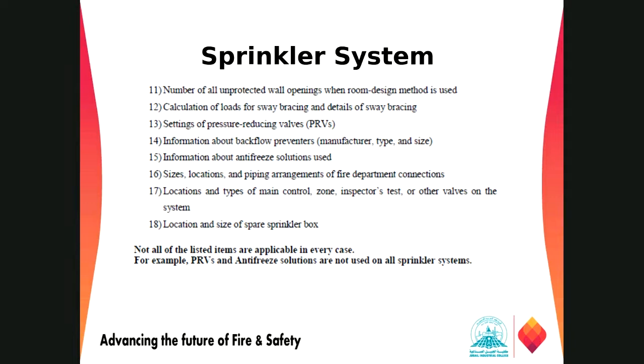Point number 11 talks about unprotected wall opening. If you are talking about the room design method, right? Remember, we studied the room design method in the previous fire protection design course. That room design method required the passive fire protection system, right? The fire barriers, which will not allow heat to go from one area to another. So for that case, we need to protect the wall openings and all with some fire-rated barriers.